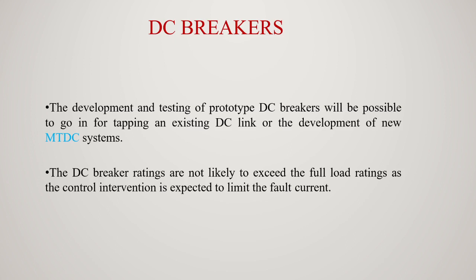Now let us see about DC breakers. With the development and testing of prototype DC breakers, it is possible to go for tapping of an existing DC link or the development of new MTDC systems. Parallel rather than series operation of converters is likely as it allows certain flexibility in the planned growth of a system. DC breaker ratings are not likely to exceed the full load ratings as the control intervention is expected to limit the fault current.